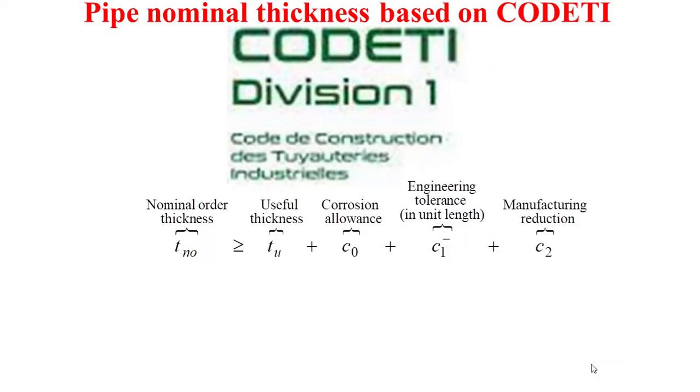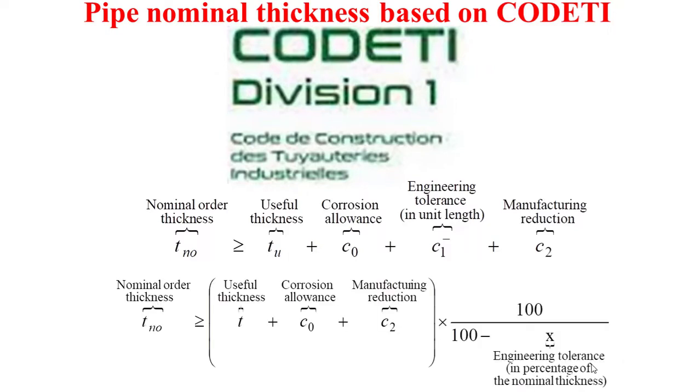When the engineering tolerance is not in unit length, but is in percentage of the nominal order thickness, this nominal order thickness should be no less than the useful thickness plus the corrosion allowance plus the manufacturing reduction.